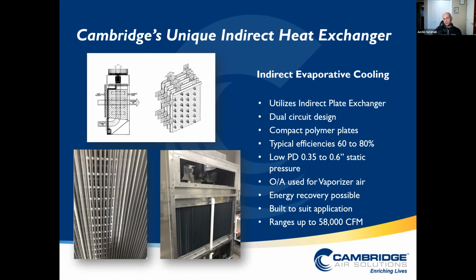One stream is for evaporation purposes — what we call scavenger air — which we discharge out the top and throw away. The other stream, shown by these arrows on the side, is fresh air from outside. We pass it through a polymer channel so it never comes into contact with the water. That way we can cool the air without adding humidity to the space.